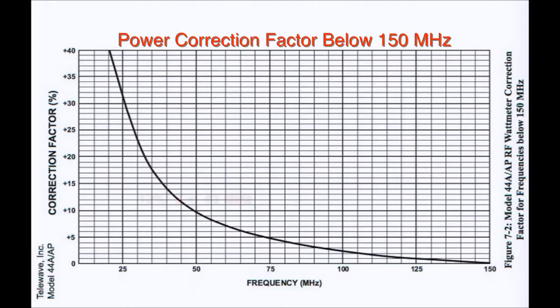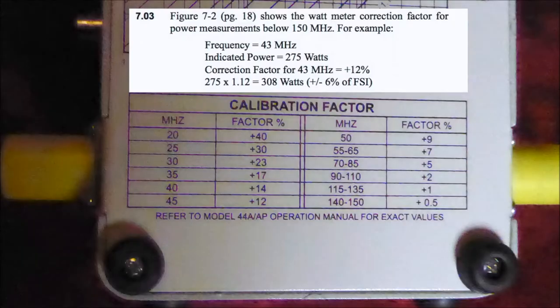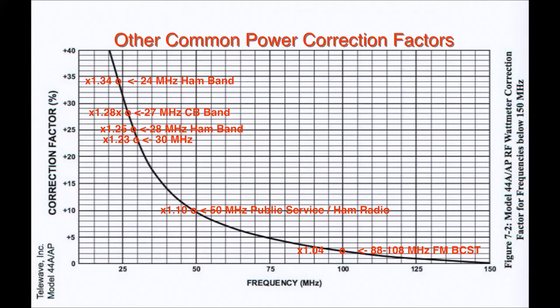If we want to take a power measurement at 43 megahertz, that gives us on the line here 12%, so 1.12 is what you multiply by. Here we have 43 megahertz. We get 275 watts on the meter. The correction factor is 1.12, which gives us 308 watts, and that's plus or minus 6% of the full-scale indication.